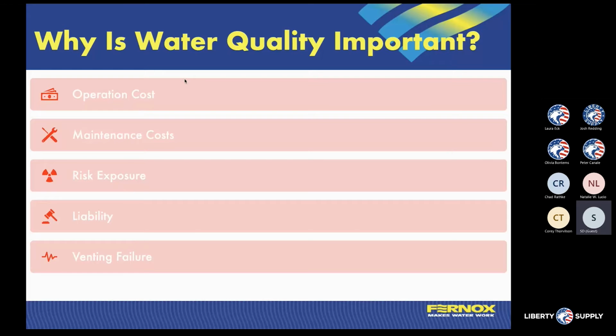So that brings up liability from the standpoint of failures. If we're talking about a boiler heat exchanger and we plug it up with water quality issues, we're going to increase our vent temperatures and potentially fail our venting, which creates another status of liability. So we were talking about all those different components of why we are doing this, or what the purpose of water quality is. It's not only something to do or just having the ability to keep a clean system, but it also has some counter effects and some financial costs to the system owner.